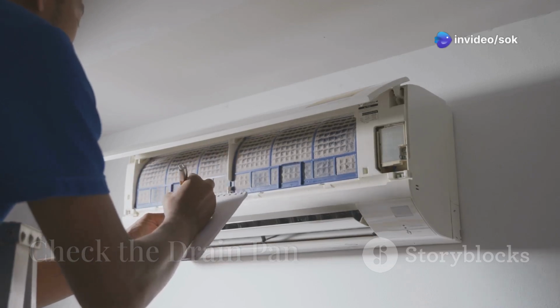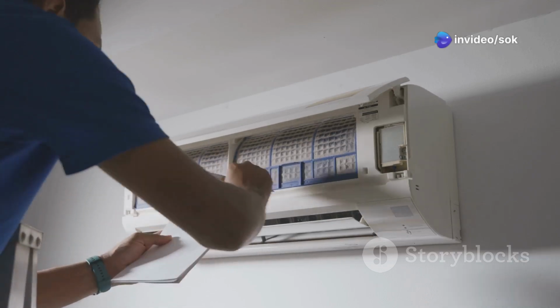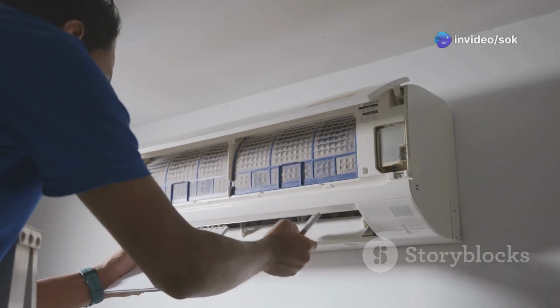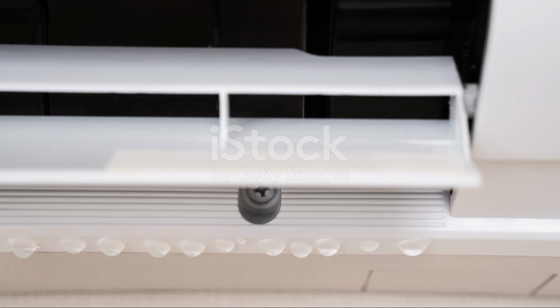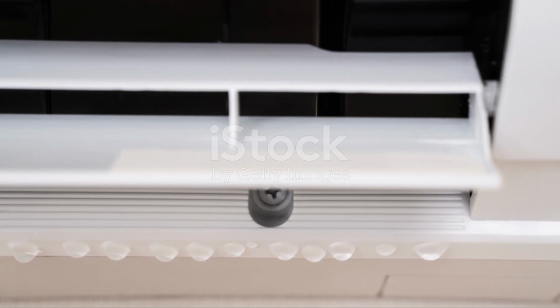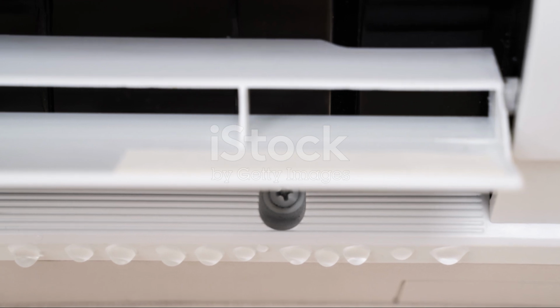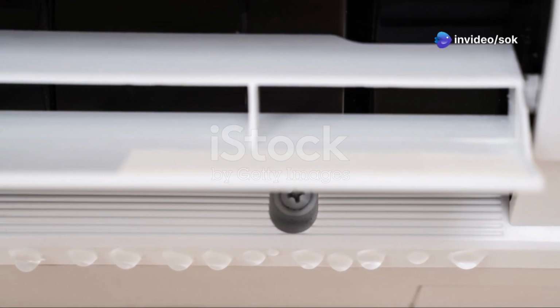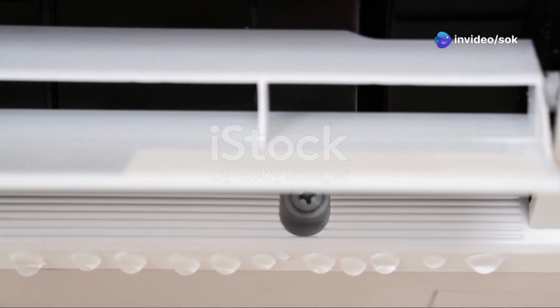Next, check the drain pan. This is a crucial step in maintaining your air conditioner's efficiency and preventing potential water damage. The drain pan collects condensation from your unit, and if it's full or dirty, water might leak out. A full drain pan can cause overflow, leading to water damage in your home.